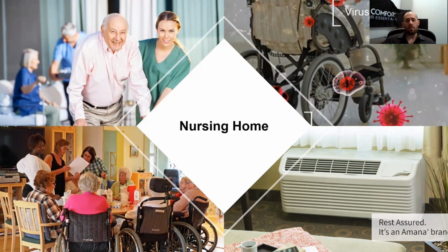Historically, calls from nursing homes and retirement communities are for odors. We want to eliminate whatever odor is going on. Today, we find it's more about protecting the occupants and the workers. Now, these rooms typically have small PTAC units, and this is where we'd use that small air purifier designed for PTACs. Nursing homes usually have common areas with larger air handling units where they bring in fresh air, and if need be, we can add air purifiers to those units as well.